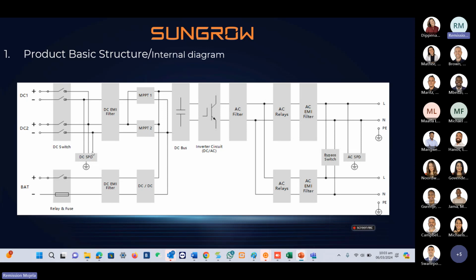And then we have the DC switch, which has SPDs, and then we have the DC EMI filter, and then we have our MPPTs, and then we have our DC bus. We have our battery input, which has a battery relay, and a fuse, a DC EMI filter, and a DC to DC boost that directly connects to the DC bus. And then we have the inverter side, and then the AC filter, then the AC relay, the AC EMI filter, the bypass, and the AC relay that goes to the backup.